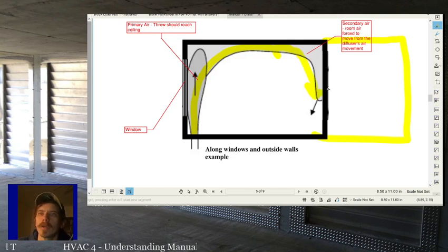And there's no hard and fast rule. I can't say, if it's 20 foot wide, you want 12 foot of throw. But you just kind of say, okay, this is a bigger room. I need more CFM. Do I want to pick two 80 CFM diffusers, or do I want one single 100 CFM? Or do I even want one single 120 CFM because it's such a big room? Again, generally, I try not to go over 100 CFM per register, right?